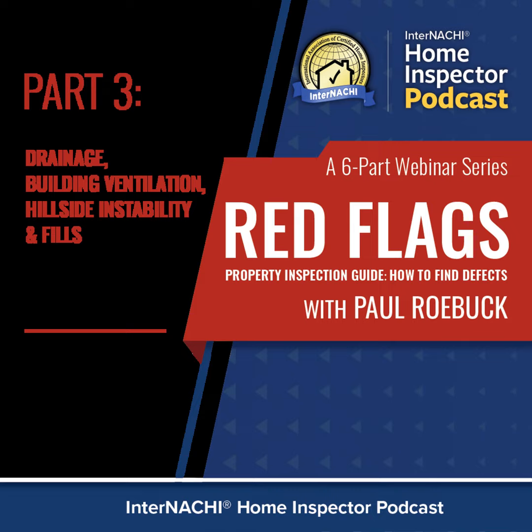Attics containing appliances shall be provided with an opening and a clear unobstructed passageway large enough to allow removal of the largest appliance, but not less than 30 inches high by 22 inches wide, and not more than 20 feet in length measured from the center line of the passageway from the opening to the appliance. What does that mean? If you have an air handler in the attic space, the opening for you to gain access to it has to be large enough for that piece of equipment to be removed and replaced. So if you have an air handler sitting in the attic and, let's just say, it's a 30 by 36 inch, 6 feet long piece of equipment, that opening has to be big enough for that piece of equipment to come out and put a new one in.